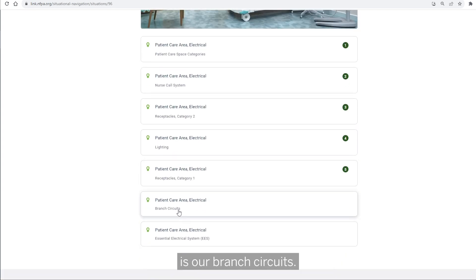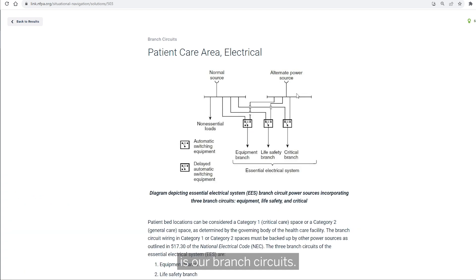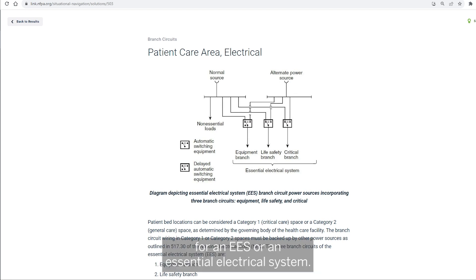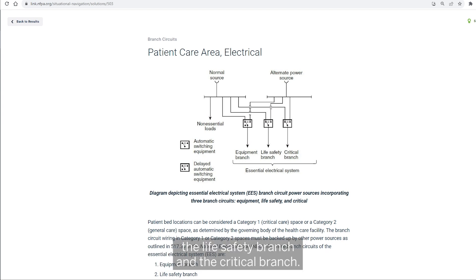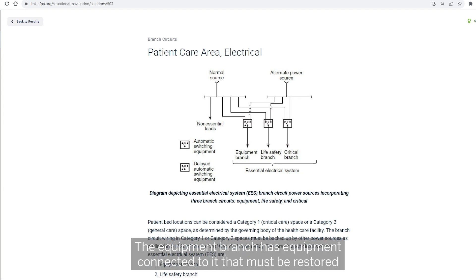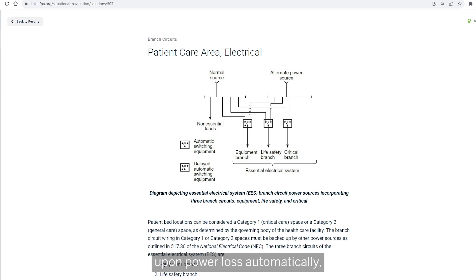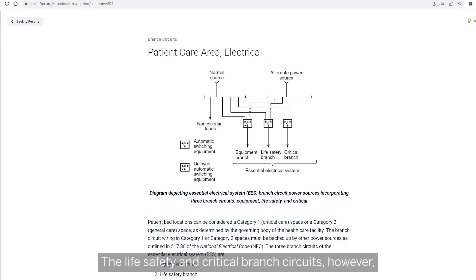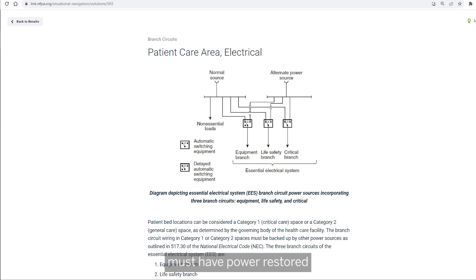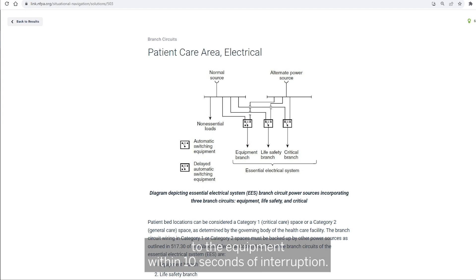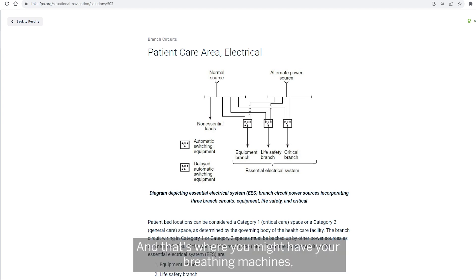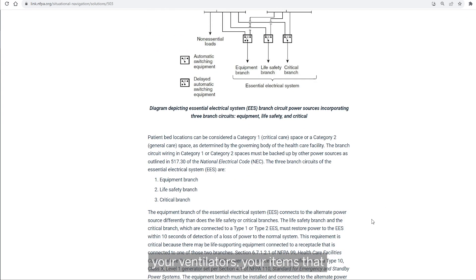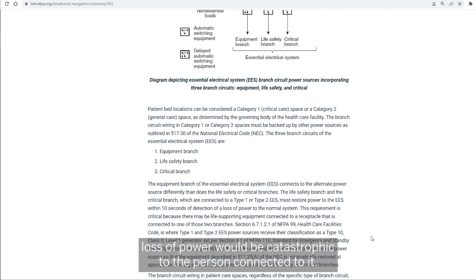Next, we're going to jump into branch circuits. There are three branch circuits for an EES, or essential electrical system: the equipment branch, the life safety branch, and the critical branch. The equipment branch has equipment that must be restored upon power loss automatically, but done so at time-lag intervals — they come on in stages. The life safety and critical branch circuits, however, must have power restored within 10 seconds of interruption. That's where you have your breathing machines and ventilators — items where loss of power would be catastrophic to the person connected.